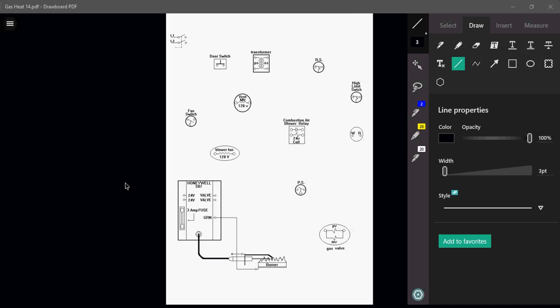Okay, on a lot of your high efficiency furnaces, the inducer motor is going to be there, but with that inducer motor, you're going to have a pressure switch. That pressure switch is located right here. That's the symbol for it. Really, what that pressure switch is doing, it's a proving switch. It's proving that the inducer motor is actually spinning and working, but it's also proving that there is a pressure difference inside the heat exchanger.